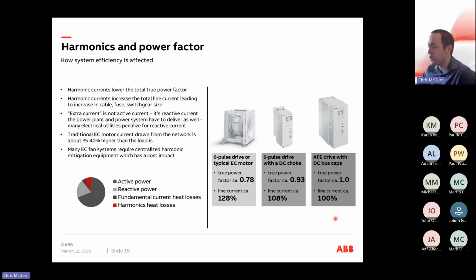And then finally, we have this special piece of equipment, which is called our ABB ultra low harmonic drive. It has an active front end filter on it, which prevents harmonics from occurring. So it's a special piece of equipment that changes your true power factor to 1.0. So you're getting the full amount of power that you require, and it's actually being used on whatever it is you're trying to do, whether it be fans or pumps or whatever. So it's an important topic that's really coming to fruition in the last couple of years.